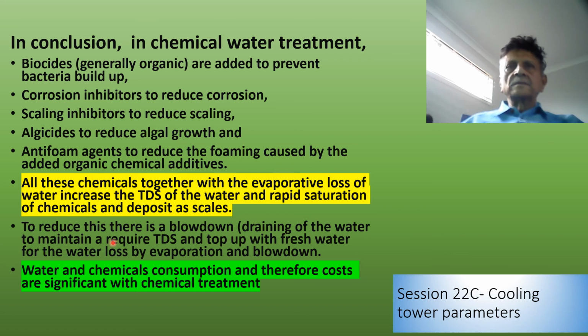When you add more water, you are obviously reducing the concentration of the biocides, corrosion inhibitors, scaling inhibitors, algicides, anti-foaming agents, etc. So you also have to top up these chemicals to the concentrations as specified by the manufacturers.